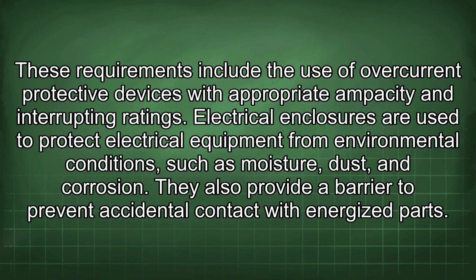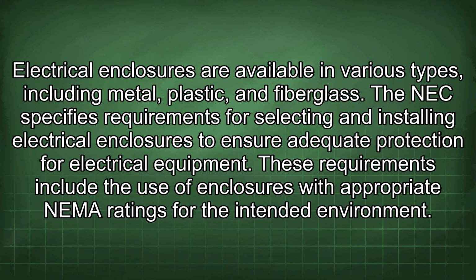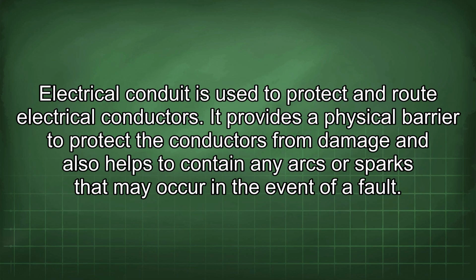Electrical enclosures are used to protect electrical equipment from environmental conditions such as moisture, dust, and corrosion. They also provide a barrier to prevent accidental contact with energized parts. Electrical enclosures are available in various types, including metal, plastic, and fiberglass. The NEC specifies requirements for selecting and installing electrical enclosures to ensure adequate protection for electrical equipment. These requirements include the use of enclosures with appropriate NEMA ratings for the intended environment. Electrical conduit is used to protect and route electrical conductors.